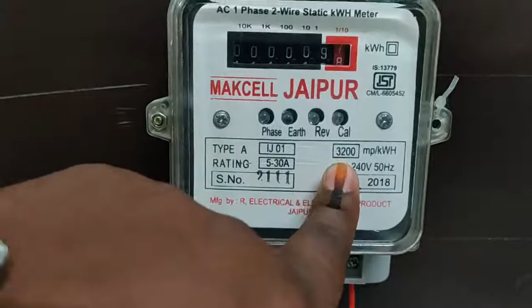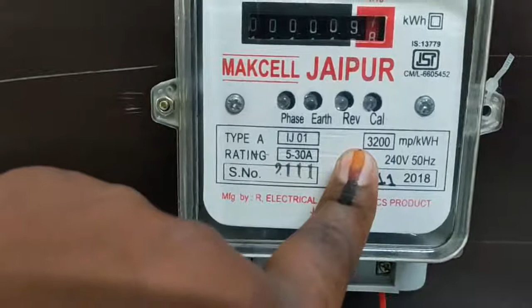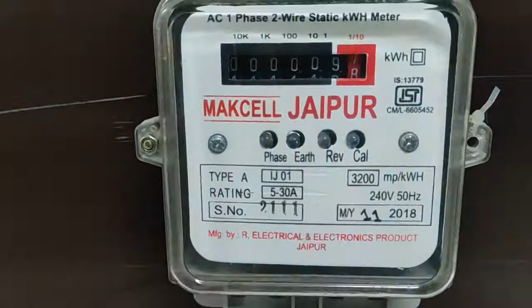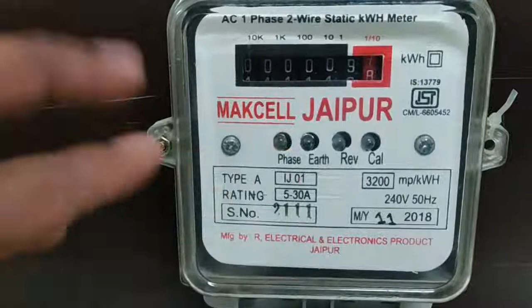So we can't wait to get 3200 revolutions, which would take very long. So we are calculating the meter constant based on 10 revolutions, and calculating the meter constant according to that value. Here we cannot see any disc, so we can't calculate the revolutions physically.